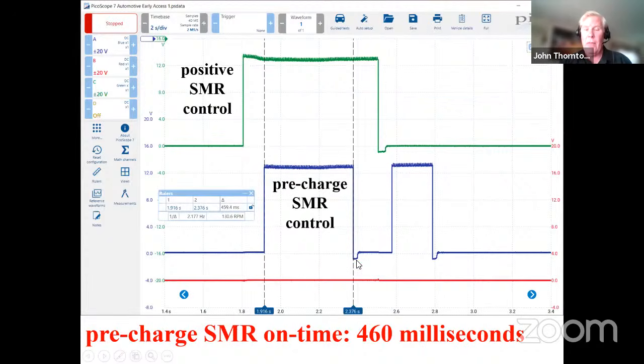Now, interestingly, if you note where my cursors are, for that 460 milliseconds, both the positive and the pre-charge, which is on the negative relay, are turned on. That means for 460 milliseconds, there should have been voltage at the inverter, or current flow to the inverter.